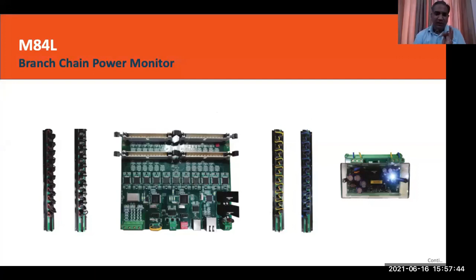This branch chain monitor again has no display. Everything comes through the CT input to the meter. All the calculations are done inside the meter through smart controllers, and through RS-485, like in the blind meter, the data gets transferred to our EMS or BMS or wherever we need it. So wherever we need retrofitting, wherever we don't have space and we want to measure properly, at very low current levels, accurate monitoring, this meter can provide.